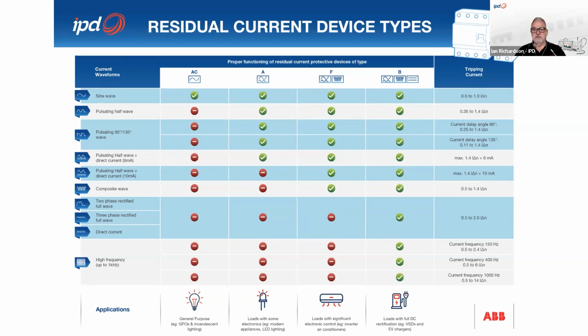The type AC and the type A RCDs have a resistance to impulses, or leakage currents and surges, up to 250 amps. But due to the more advanced loads they're designed for, the type F and type B have a higher resistance to impulses, up to 3000 amps. So this provides a really good resistance against nuisance tripping.